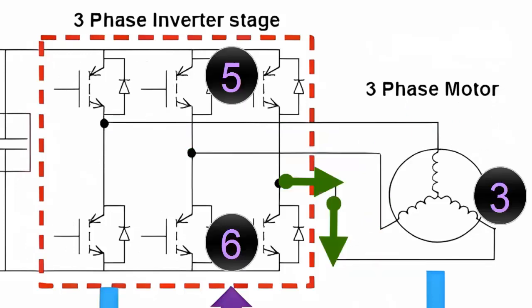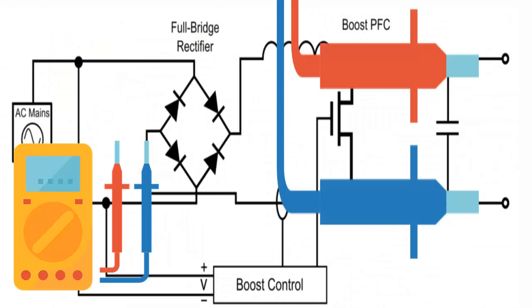Additionally, the IPM circuit controls the frequency or the number of times the transistors allow the passage of current, thus regulating the speed of the compressor motor.